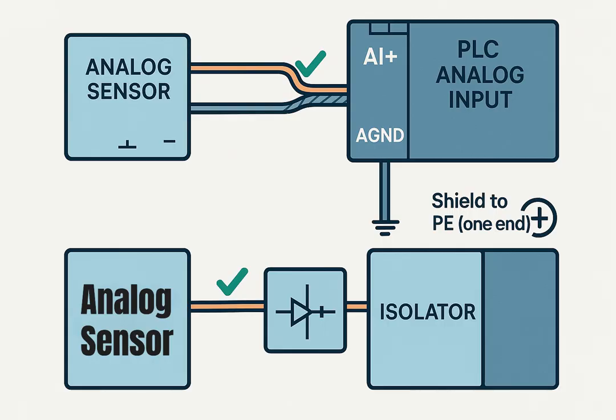If using shielded cable, connect the shield to PE at one end only, typically at the PLC or cabinet side. Do not ground both ends of the shield to avoid ground loops. Use PE for device enclosures, sensor bodies, the cabinet frame, and the cable shield, as a single point connection. Do not use PE as the return path for the analog signal. When wired correctly, the analog signal is referenced to a cleaner ground, and noise from VFDs and power devices is less likely to enter the signal path. The HMI trend becomes much smoother and more stable.